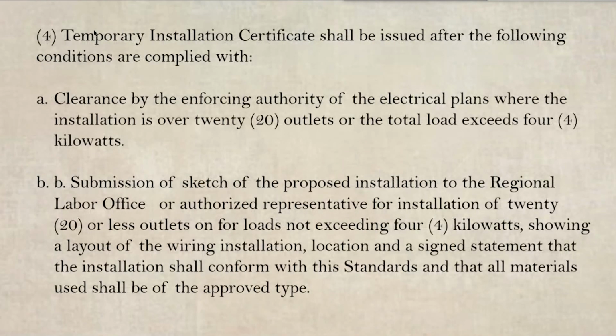Temporary installation certificates shall be issued after the following conditions are complied. Kapag ang outlets na ilalagay ay over 20 at nag-exceed ang load niya sa 4 kilowatts, kailangan may clearance ng enforcing authority of the electrical plans. Kapag naman mas mababa sa 20 outlets ang ilalagay at mababa rin sa 4 kilowatts ang loads, sketch lang ng proposed installation ang ibibigay sa Regional Labor Office. Pero may nakalagay dito ang layout of the wiring installation, location, and sign statement that the installation shall conform with the standards and all materials shall be of the approved type.